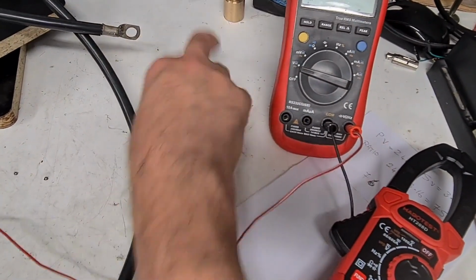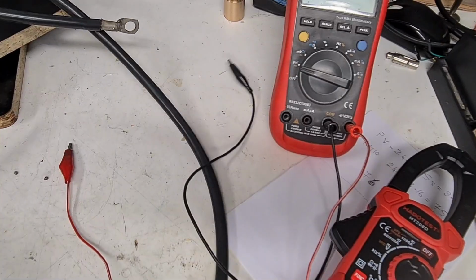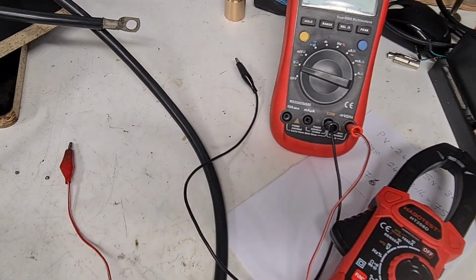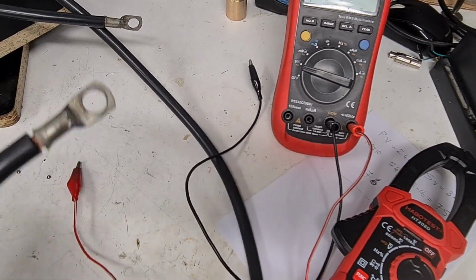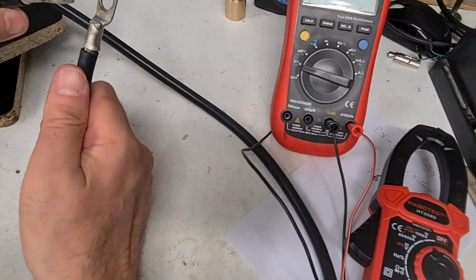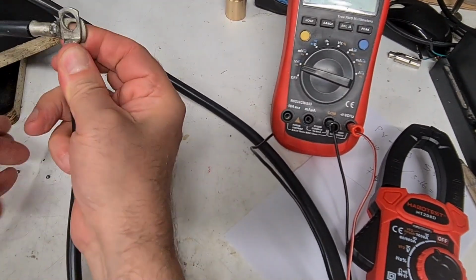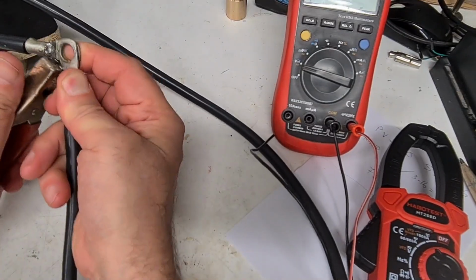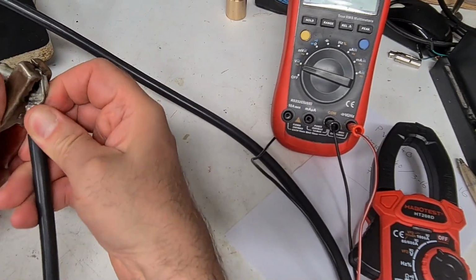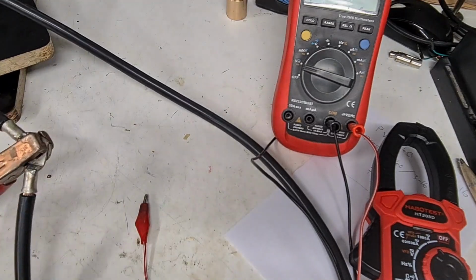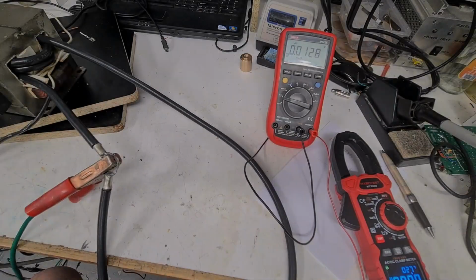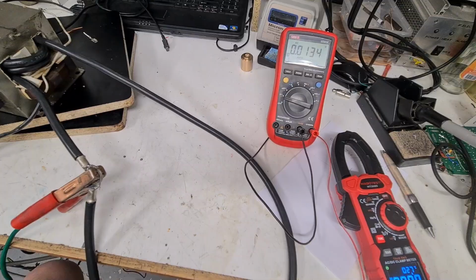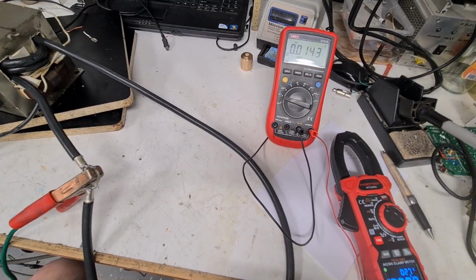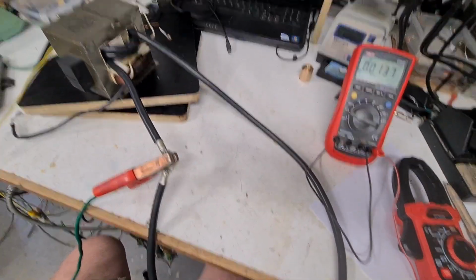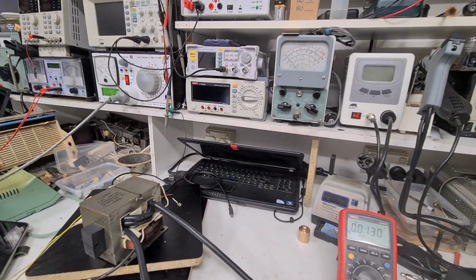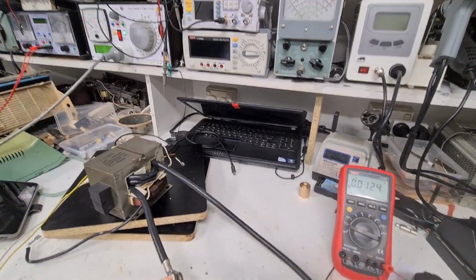I am going to short out the secondary windings. I can only do this because I've got a variac that can handle 8 amps. Otherwise you cannot really do this test properly without overheating things and blowing fuses. As you can see, I've got the primary hooked up to the variac, and it's at 0 volts.